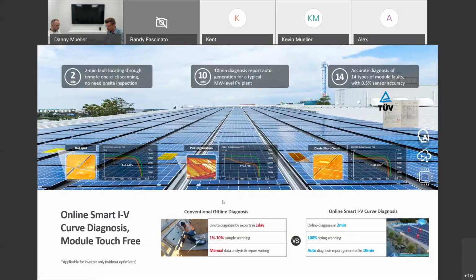And that's something which is extremely powerful, maybe not in year 1, maybe not in year 5, but once your system gets older, talk about year 10, year 15, year 20, that having a system where you can super easily check the whole system and not just a small sample size where you send a guy with an IV Curve Tracer, which is whatever, $14,000, $15,000 at 1,500 volts out, and they test a few strings in the system at high cost. No, you can actually do it from your office around noon when the sun is up and have that data available. I'm certainly happy to walk you through such an operation on a test system.